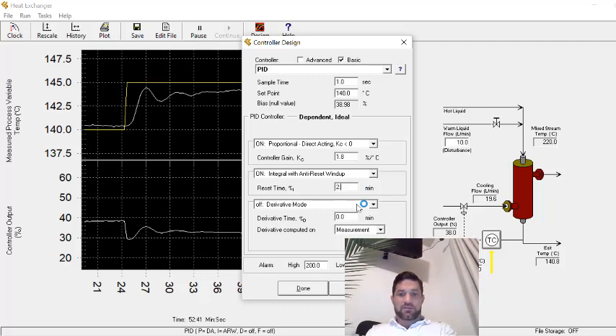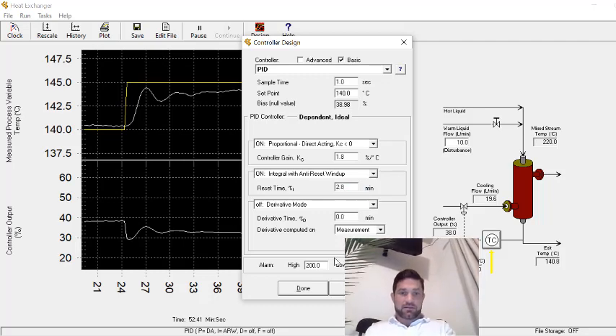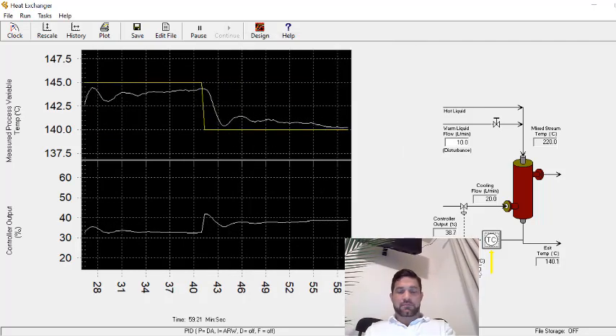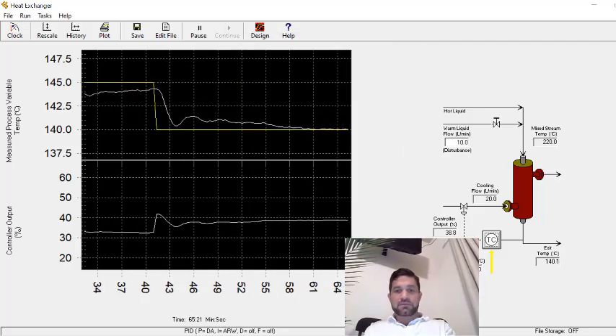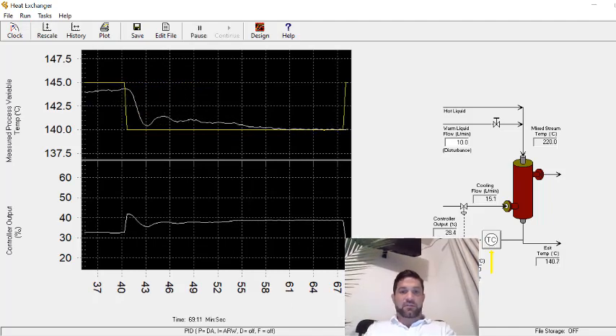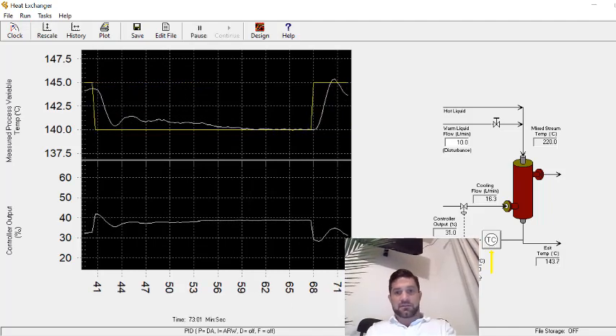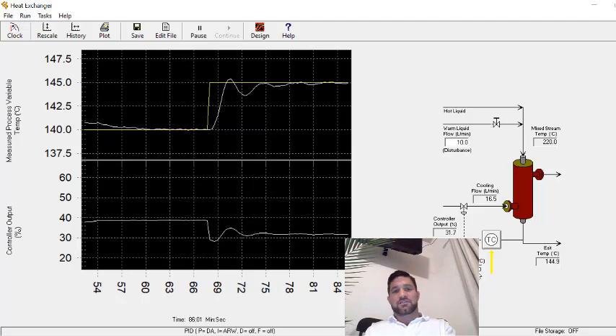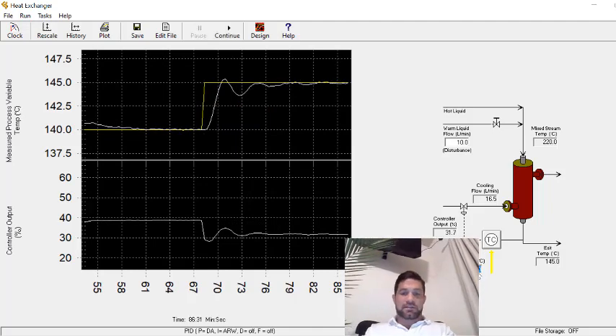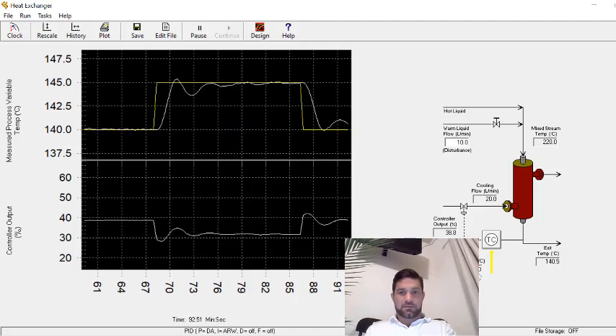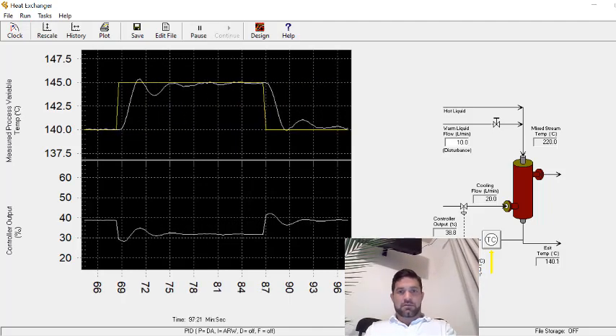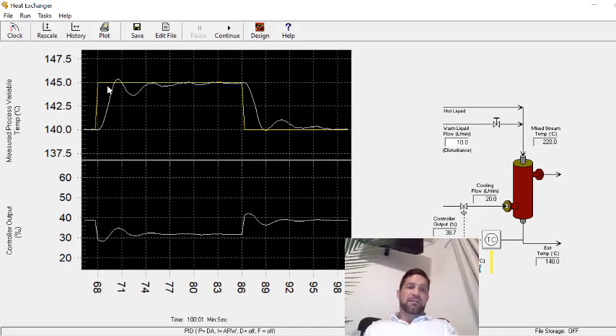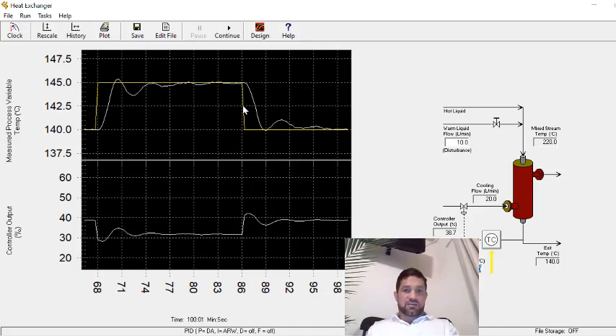So I'll set τI to 2.8 and gain to 1.8, and let's see how the process responds with a step to 145. Look, and then step back down. It's not too bad for the heat exchanger.